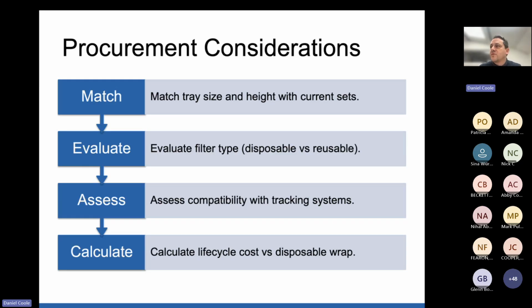Evaluate the filter type. What are you comfortable with? As I mentioned, there are long-term filters out there that are PTFE and validated for longer cycles, but how do you control that, and how do you know how many cycles the filters have gone through? With a disposable, you dispose of it. Yes, it's a disposable piece of paper, which is obviously not ideal from a sustainability perspective, but you do have the reassurance that you have a new filter every single time.